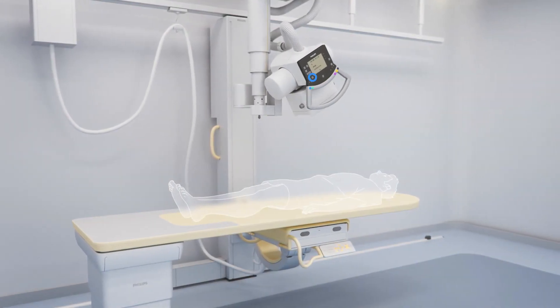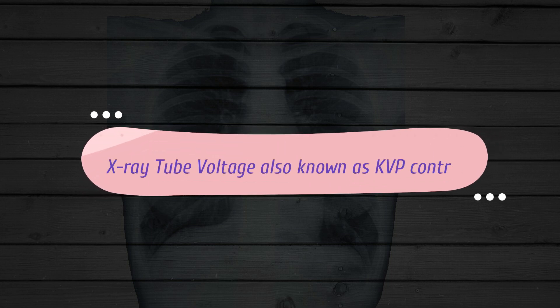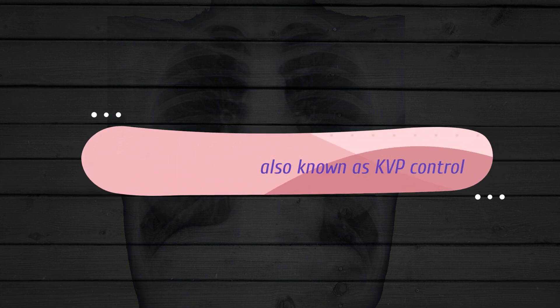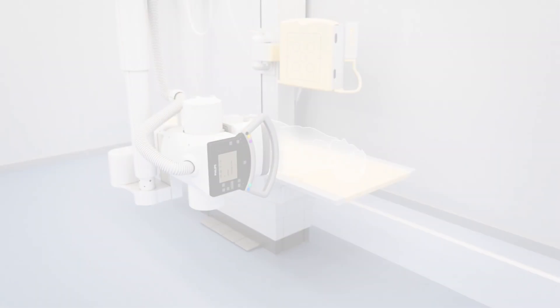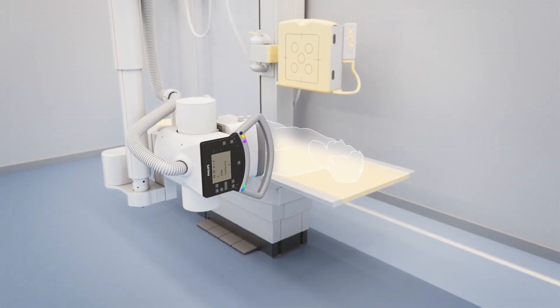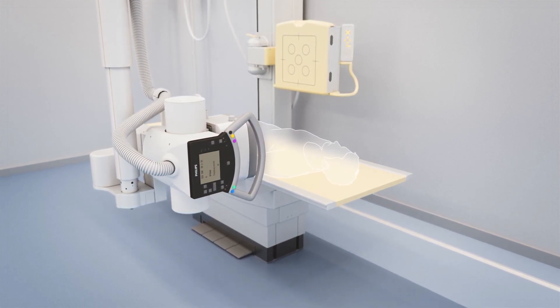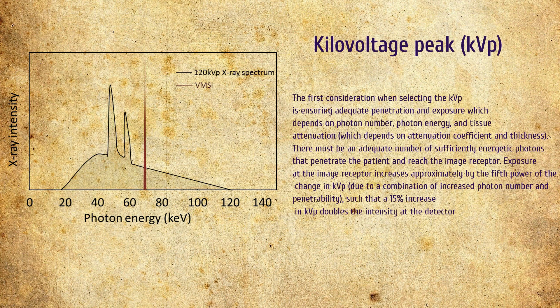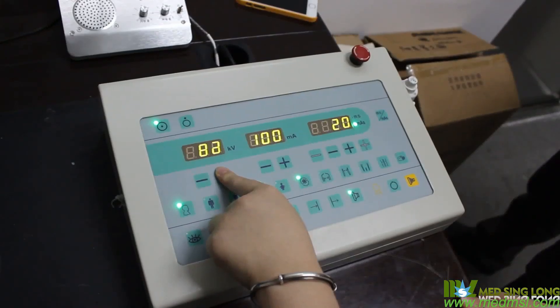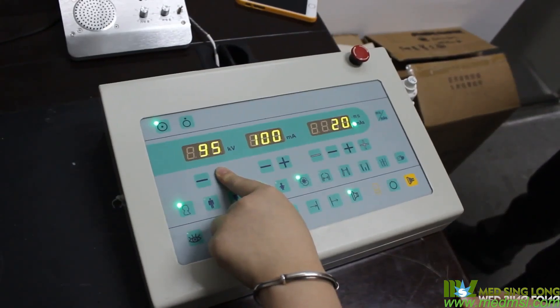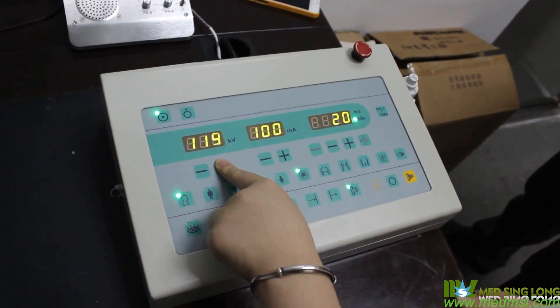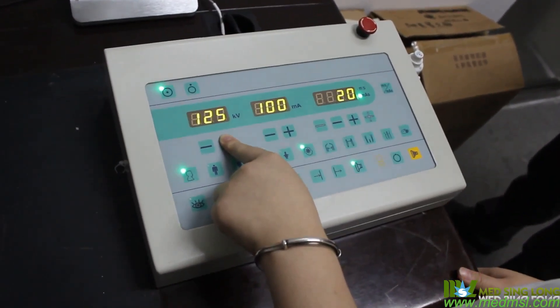Let's look into the effect of changing x-ray tube voltage, also known as KVP control. KVP refers to the maximum high voltage applied across an x-ray tube during the creation of x-rays. During x-ray generation, surface electrons are released from a heated cathode by thermionic emission. The applied voltage accelerates these electrons toward an anode target, ultimately producing x-rays when the electrons are stopped in the anode. Thus the KVP corresponds to the highest kinetic energy of the electron striking the target and is proportional to the maximum energy of the resulting x-ray emission spectrum.